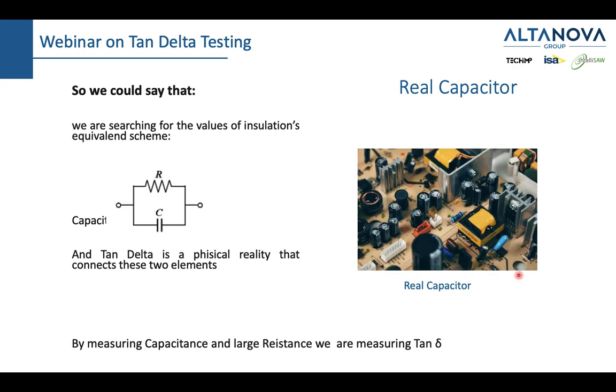while modeling the insulation. So here we have our real capacitors used on a PCB, and we can say that we are actually searching for the values of insulation's equivalent scheme. So since we can model our insulation as resistance and capacitance connected in parallel, we actually are searching for resistance and capacitance, and tan delta is a physical reality that somehow connects these two elements. So by measuring resistance and capacitance, we measure tan delta.